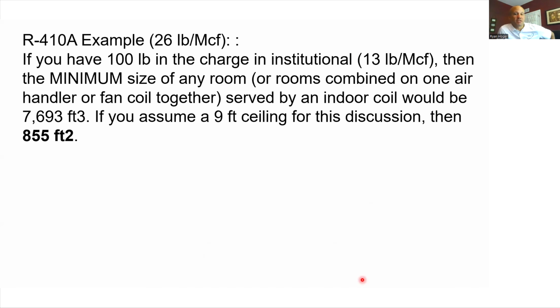So what do we normally do with this? Here's the math. There's only two times we'll do any math today. This is one of those times. This is a real project from a little over a year ago. It was a large VRF system, 98 pounds. At the time, I rounded it off to 100 pounds. It was using 410A, so the limit would have been 26, but it was a senior living center, so my limit was 13 pounds per million cubic feet.